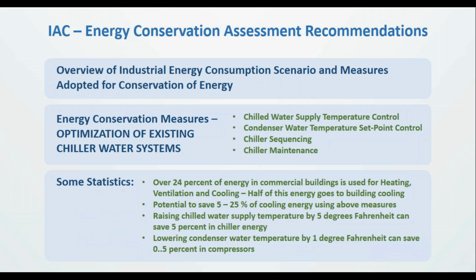So we have recommended over the period of years several energy conservation measures for buildings. Yes, HVAC associated with buildings as well as manufacturing plants, and those would be related, as an example, to reducing or increasing the chiller set point. So that's what we mean by chilled water supply temperature control. For example, if a chiller system is operating at 38 degrees Fahrenheit, and we think that maybe bumping it up a couple of degrees to 40 will not affect the process based on discussion with plant personnel, then we would definitely try and do that in terms of a recommendation and see how much energy can be saved.